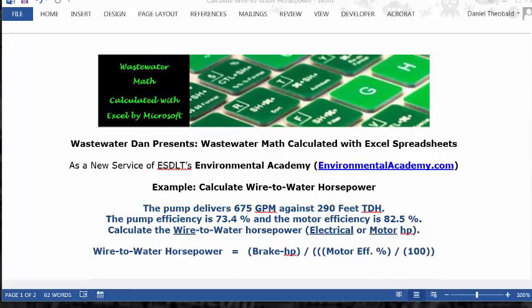today's example: calculate wire-to-water horsepower. Today's problem reads: the pump delivers 675 GPM against 290 feet TDH. The pump efficiency is 73.4% and the motor efficiency is 82.5%. Calculate the wire-to-water horsepower. Sometimes wire-to-water could be interchanged with electrical or motor horsepower.